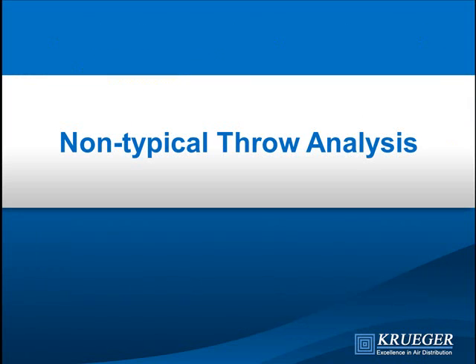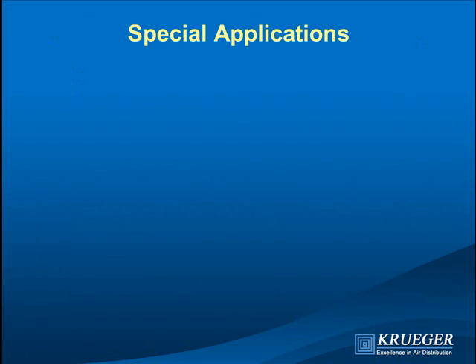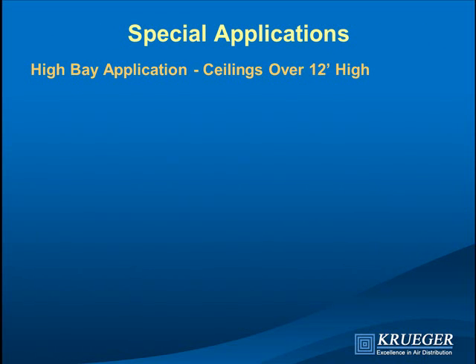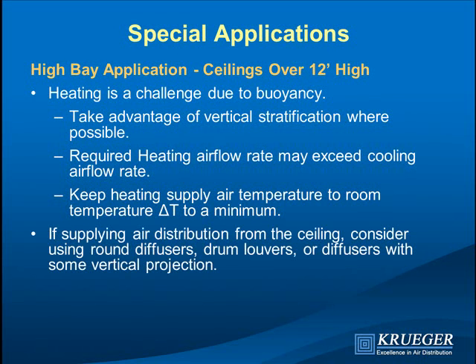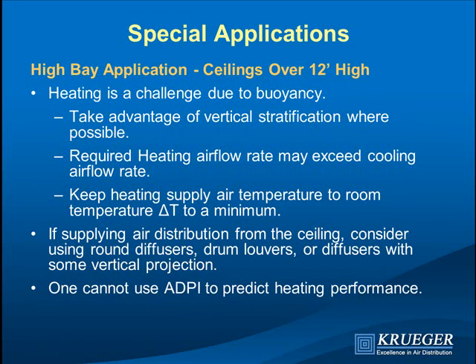Not all spaces have nine-foot ceilings with diffusers. In a high-bay application with a ceiling more than 12 feet high, heating is a challenge — hot air rises, cold air falls. Cooling will come down naturally, but for heating, put the diffuser low if possible. Calculations may show that the heating airflow rate needs to be twice the cooling airflow rate to achieve adequate throw. Keep the heating delta-T down to help increase airflow. ADPI cannot be used for ceilings over 12 feet or for heating applications.